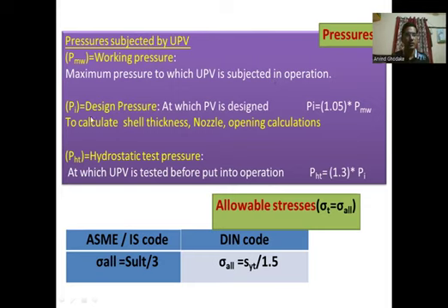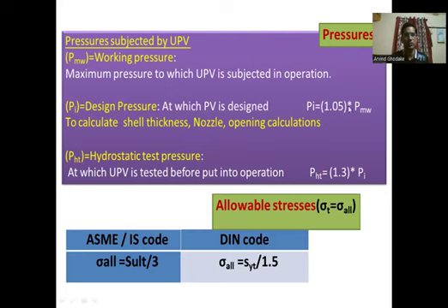Second is the design pressure, denoted by PI. The pressure at which the pressure vessel is designed is called the design pressure. The design pressure is always equal to 1.05 times the working pressure: PI = 1.05 × PMW. This design pressure is used to calculate shell thickness, nozzle, and opening calculations.